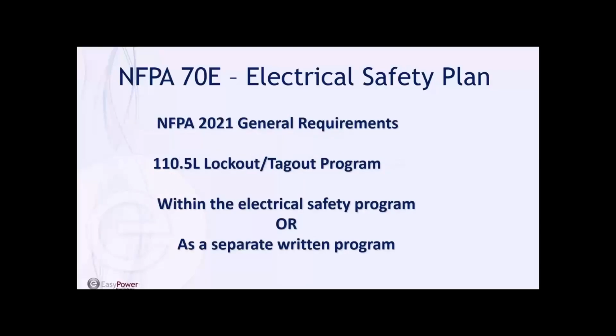Article 5L within the electrical safety plan opens the door to the lockout tagout program. It basically says you can include lockout tagout within this or write a separate written program. I'm a strong proponent of the second one, primarily because electrical is only one source of energy. All the other hazards of gravity, of potential components within large equipment that could fall, hazards of hydraulics, heat, and other things not related to locking things out electrically really do preclude that lockout tagout should be given its own separate program.